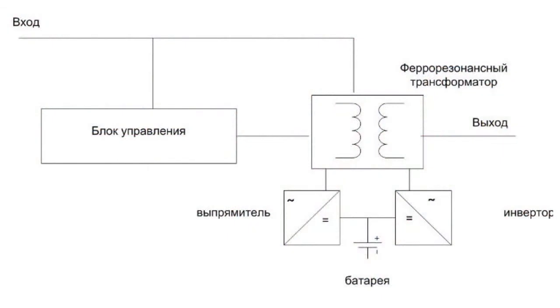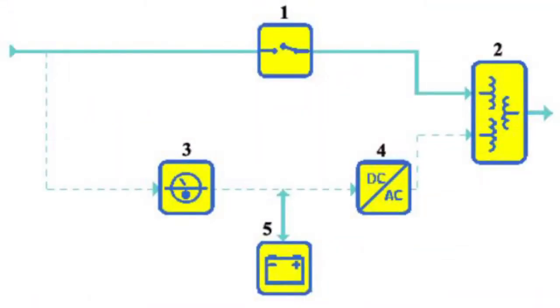So its functions are as follows. It stabilizes voltage across the UPS output. This allows operating in a wide range of supply voltages without switching into a battery operation. There is also no switching inside the UPS itself. A ferroresonant transformer controls voltage and does not require taps switching.